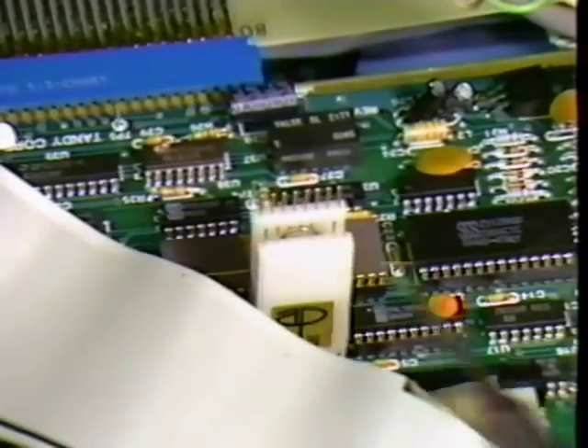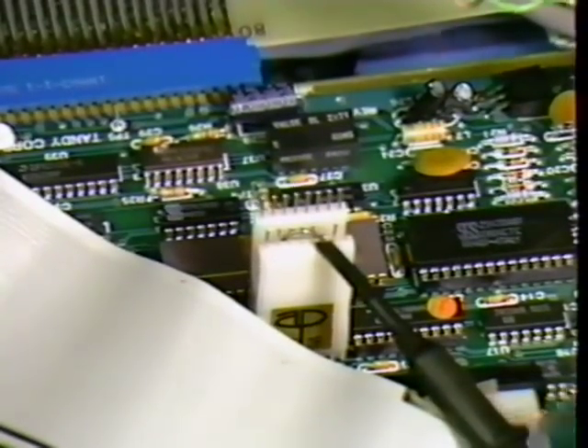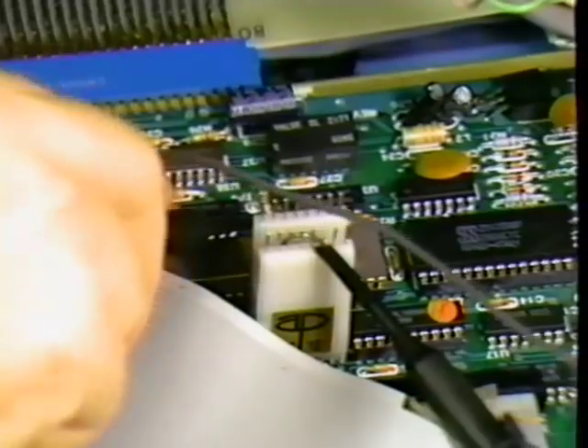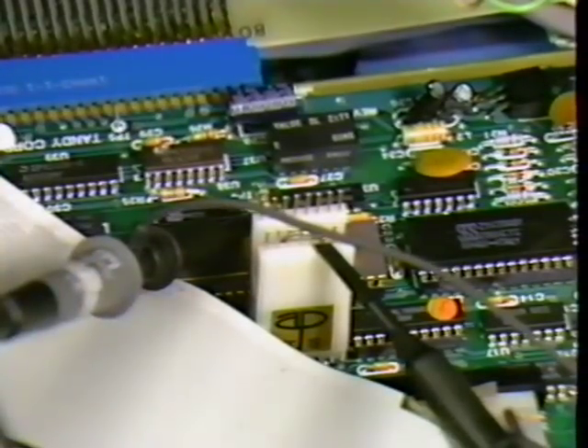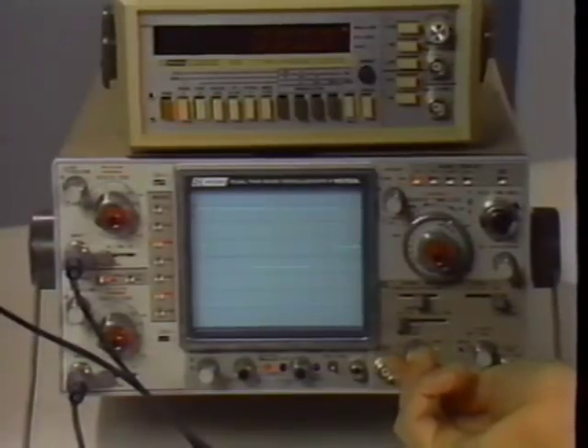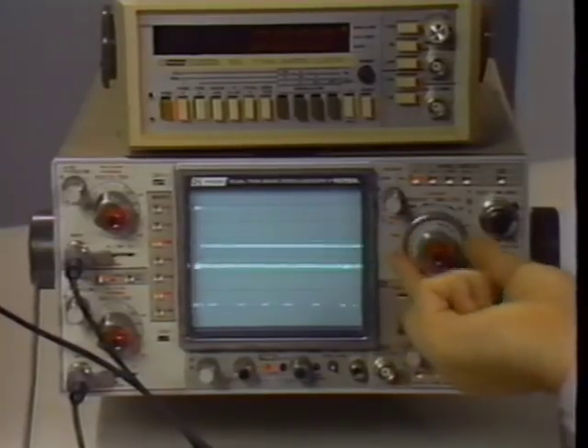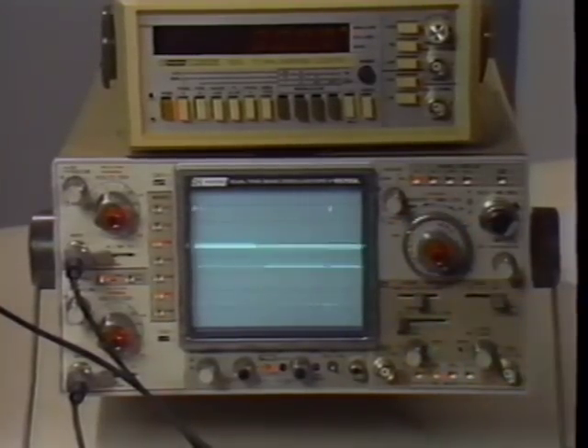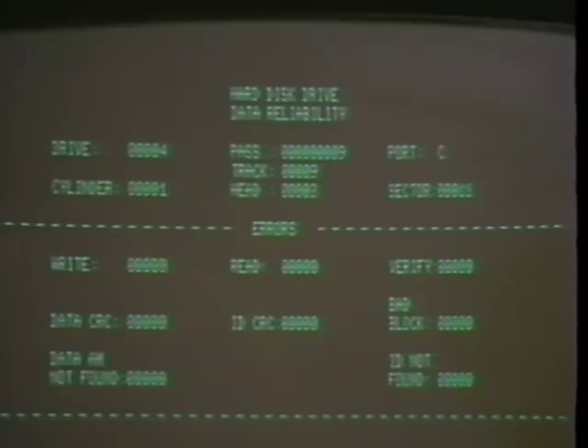Attach Channel A to the index pulse and Channel B to the D-Run signal. Check your diagnostic manual for the correct test points. Set your scope for negative trigger on Channel A, 2 millisecond per division, and 2 volts per division on each channel. Turn the D-Run adjustment pot until you can distinguish 17 D-Run pulses on Channel B between index pulses. Once this adjustment is correct, the read diagnostic should increment quickly with no errors.